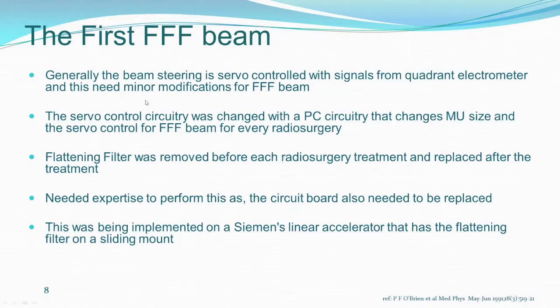And more importantly, generally the beam steering is servo controlled with signals from the quadrant electrometer. You have a quadrant electrometer there which sends the signal with which the beam is servo controlled so that your symmetry and flatness are proper. And this needed minor modifications for the FFF beam.